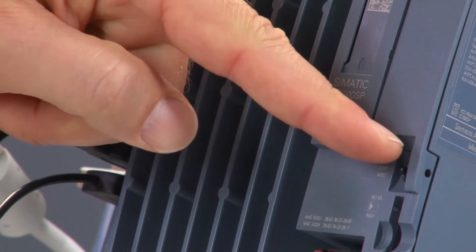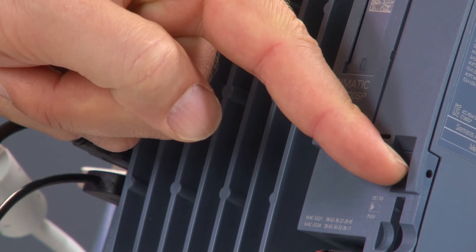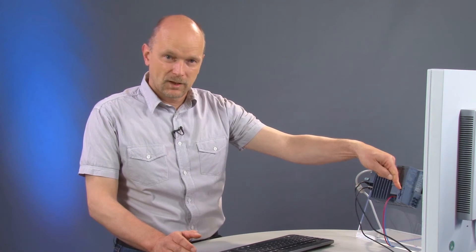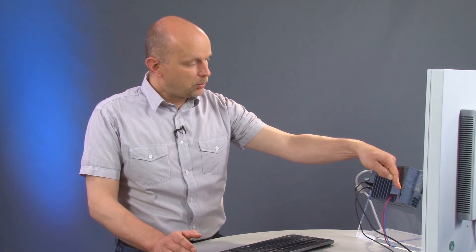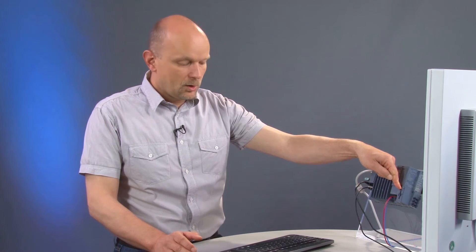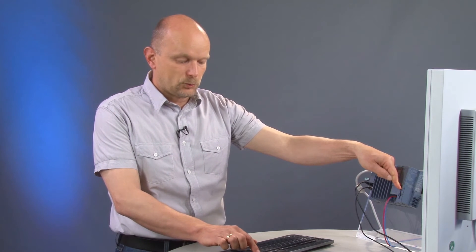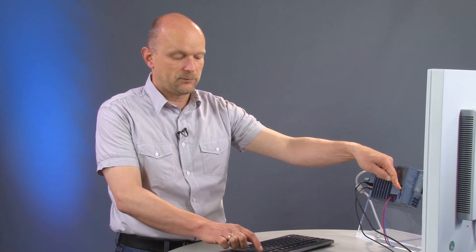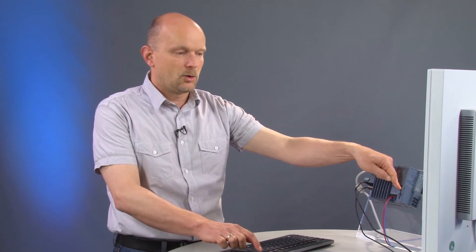When starting up the open controller, we hold the operating mode switch in the position MRES, switch on the open controller, and repeatedly press the F12 key on the keyboard to start the boot menu, as we can't see an image yet.